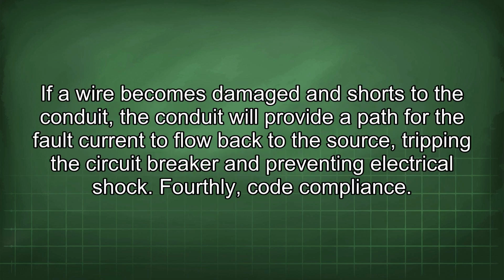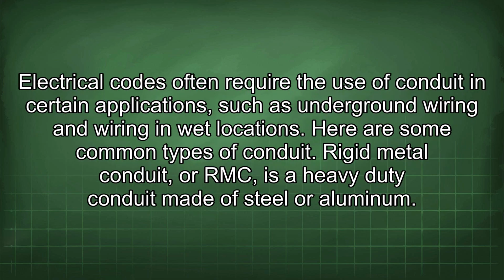If a wire becomes damaged and shorts to the conduit, the conduit will provide a path for the fault current to flow back to the source, tripping the circuit breaker and preventing electrical shock. Fourthly, code compliance. Electrical codes often require the use of conduit in certain applications, such as underground wiring and wiring in wet locations. Here are some common types of conduit.